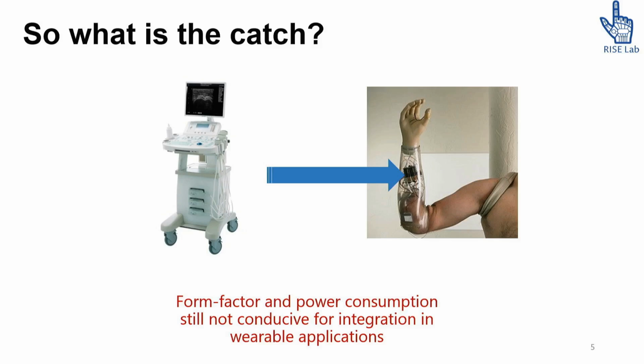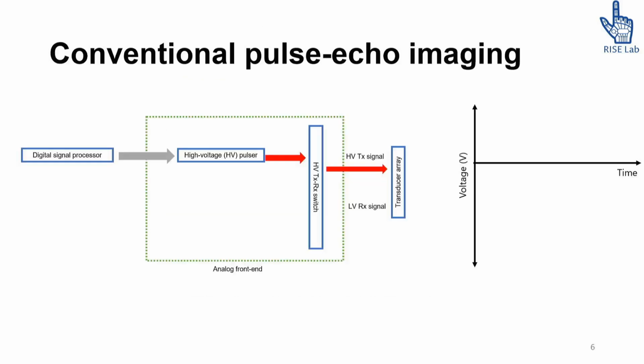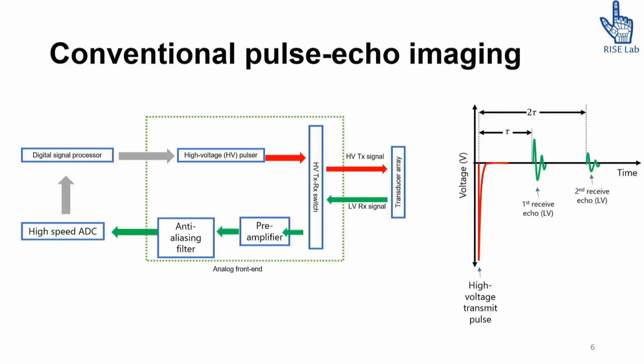So to the uninitiated, I just want to introduce you to the predominant paradigm that is used for ultrasound imaging, which is called pulse echo. In pulse echo, you have a transducer, which is a piezoelectric crystal, which you hit with an electric hammer, so you're hitting it with a high voltage pulse. This sends out a high voltage acoustic transmit pulse that travels through the tissue and gets reflected back, and you get these low voltage pulses which have to be multiplexed through a switch and then pre-amplified, and then you have all the electronics.